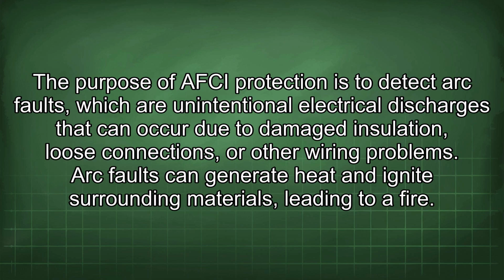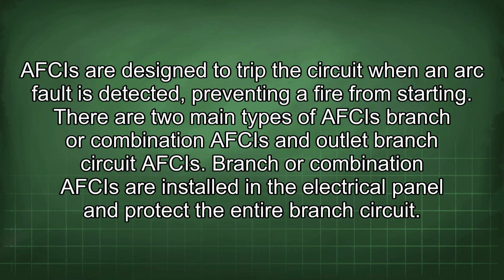The purpose of AFCI protection is to detect arc faults, which are unintentional electrical discharges that can occur due to damaged insulation, loose connections, or other wiring problems. Arc faults can generate heat and ignite surrounding materials, leading to a fire. AFCIs are designed to trip the circuit when an arc fault is detected, preventing a fire from starting.